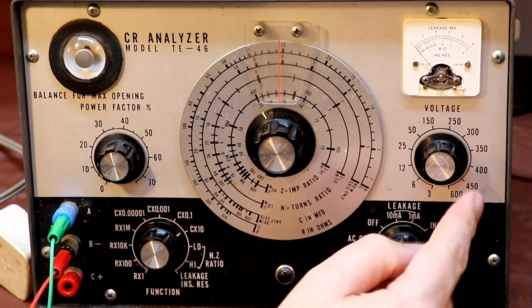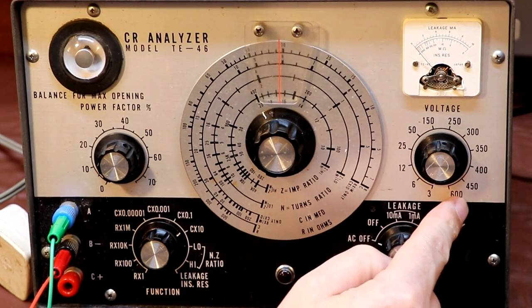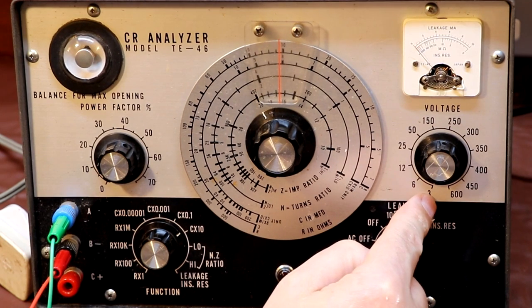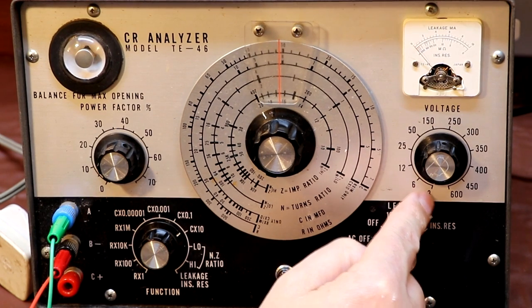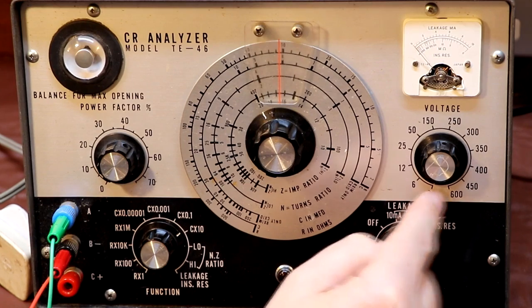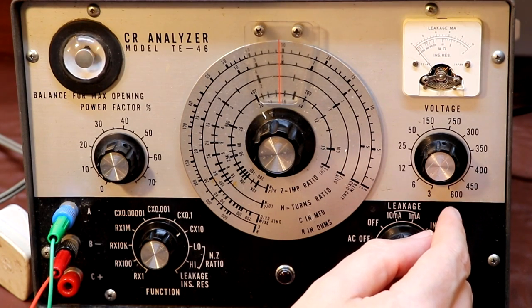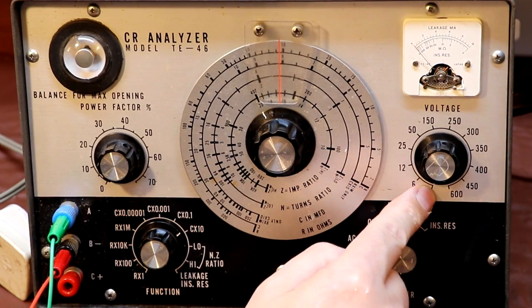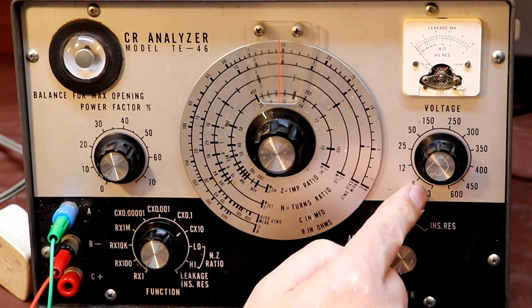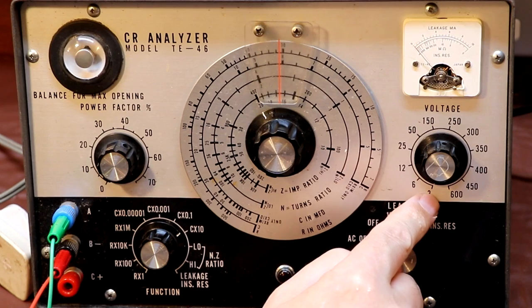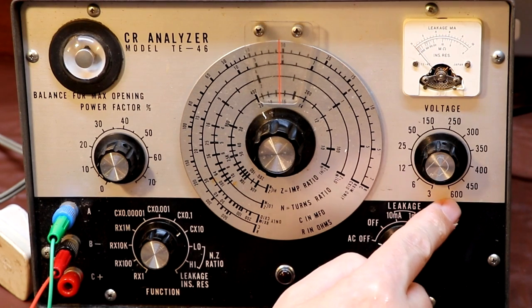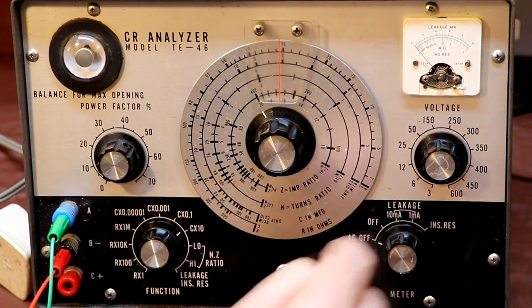But in theory, the fact that we can actually carry out those leakage tests at a range of different voltages is really useful, and that's a big advantage over the modern digital capacitance meters that work at such a low voltage they won't actually show up faults in capacitors such as leakage current. Now, the fact you can go between 3 and 600 volts is actually a real benefit for the type of work that I do.